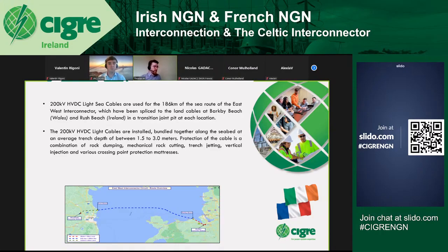These cables are bundled together along the seabed and buried approximately 1.5 to 3 meters. Protection of the cable is a combination of rock dumping, mechanical rock cutting, trench jetting, vertical injection, and various crossing point protection mattresses.